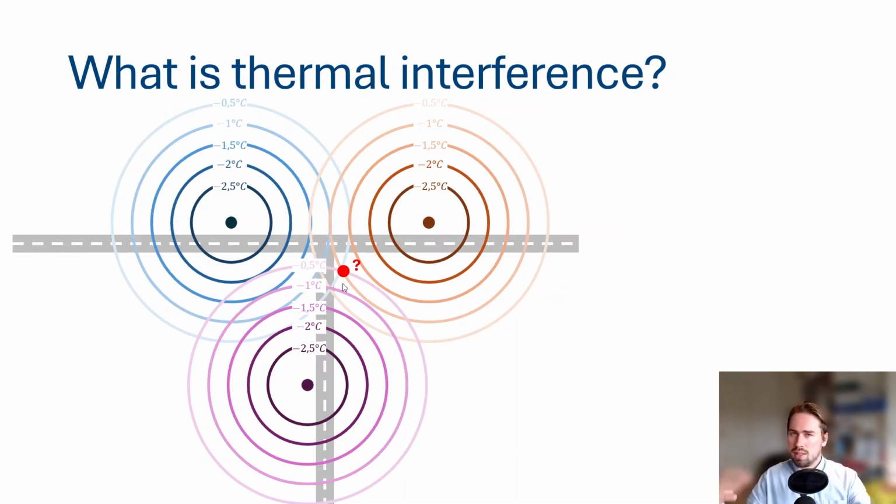So our design, where we said, okay, we make sure it stays within the limits, now our fluid temperature over the period of 25 years will be 2 degrees lower due to the fact that we have neighbors. So it is really important to take your neighbors into account when you're drilling in a densely populated area where there are already bore fields or boreholes installed in proximity.